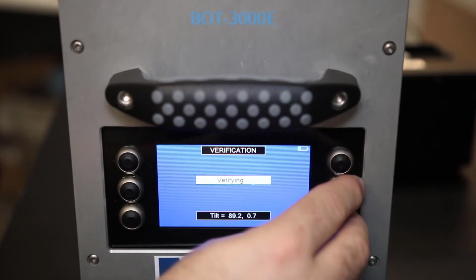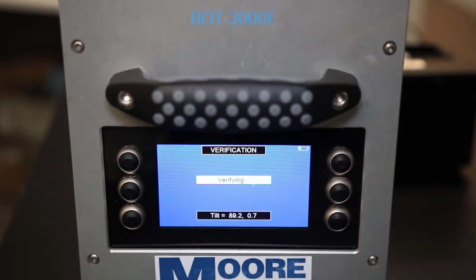After pressing Start, the BOT screen will read Verifying. Then the screen will notify you with either a passed or failed message. You now have the option to print the proof of passed verification, or select back to reset the verification. If your BOT passed verification, you may proceed with testing.